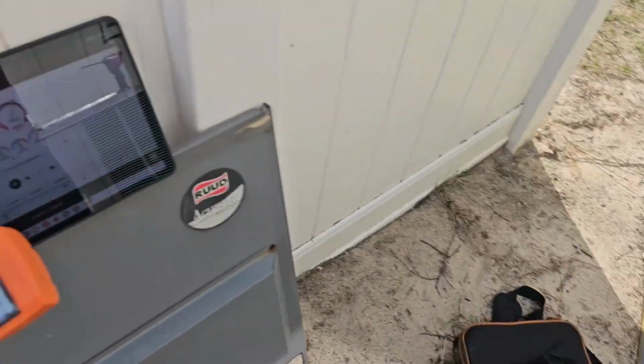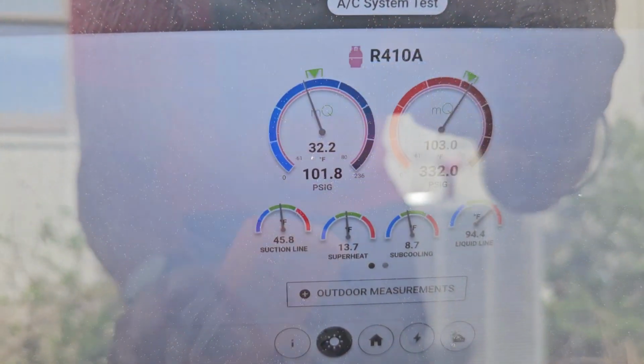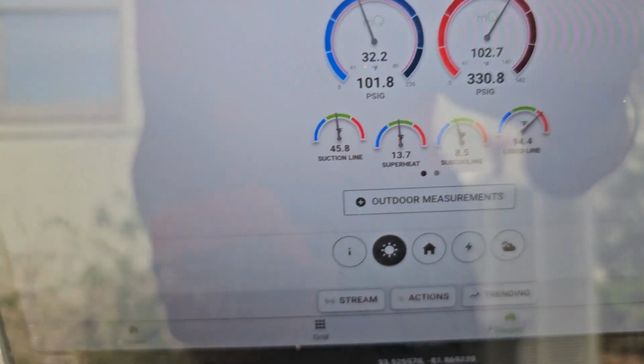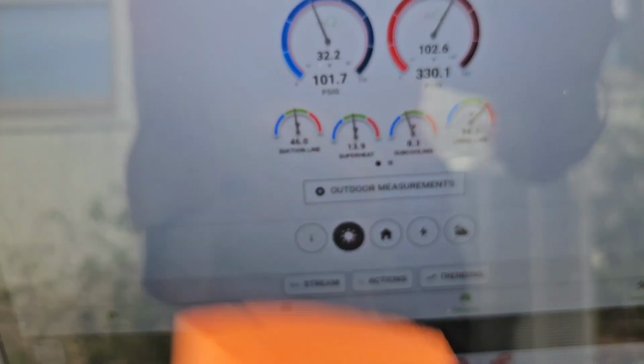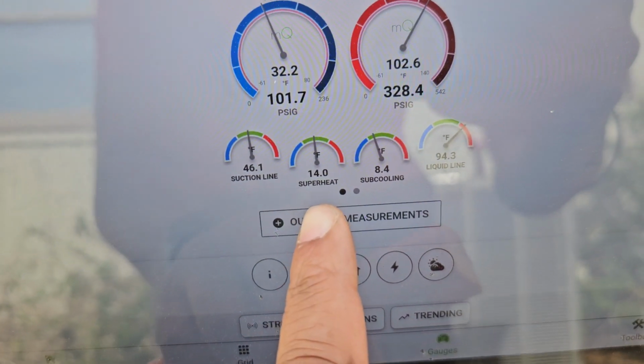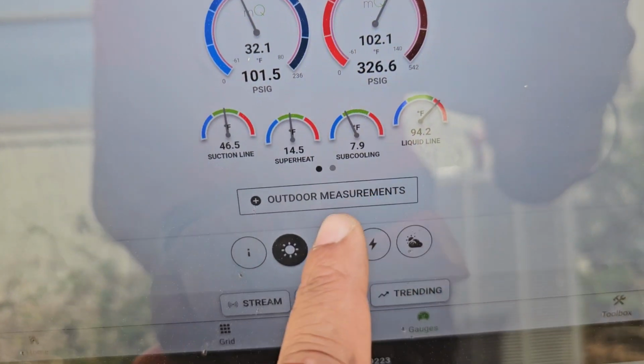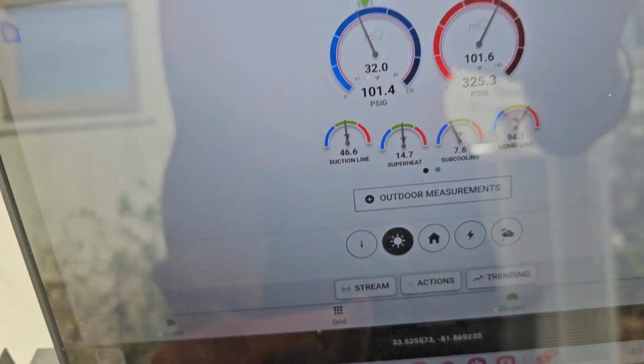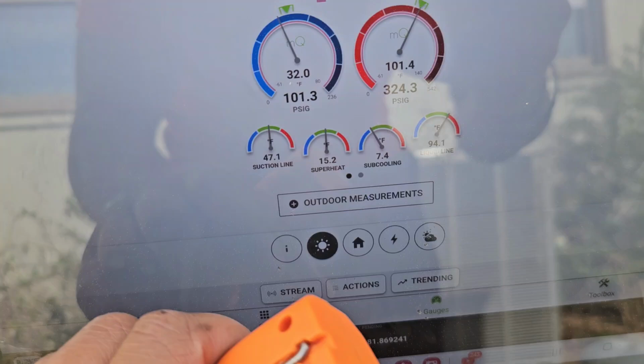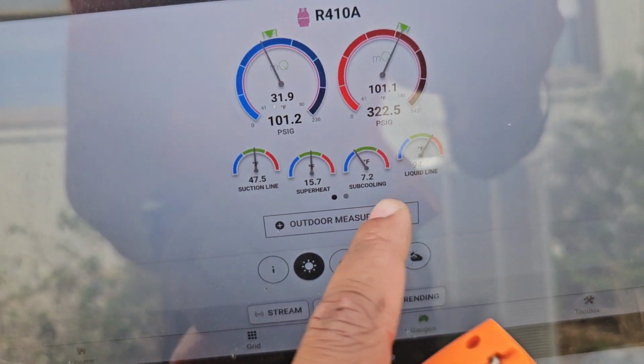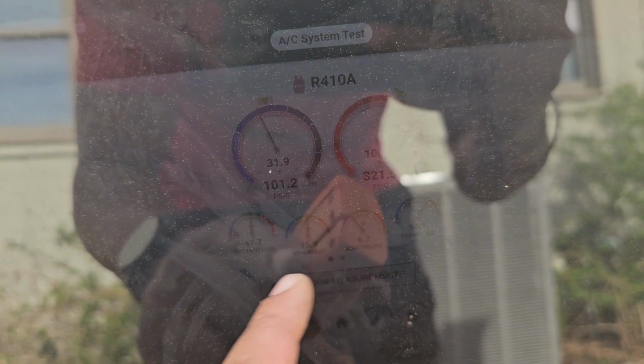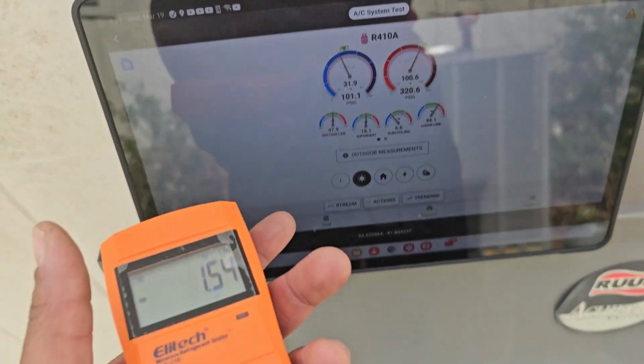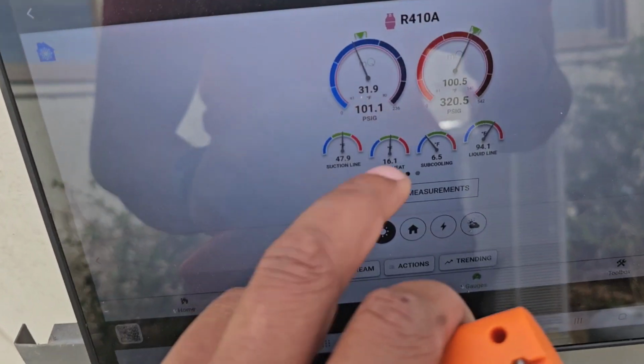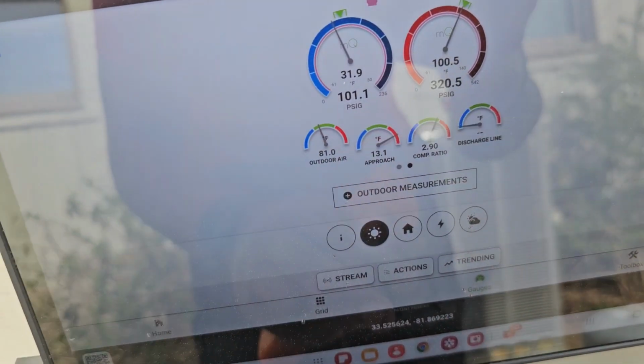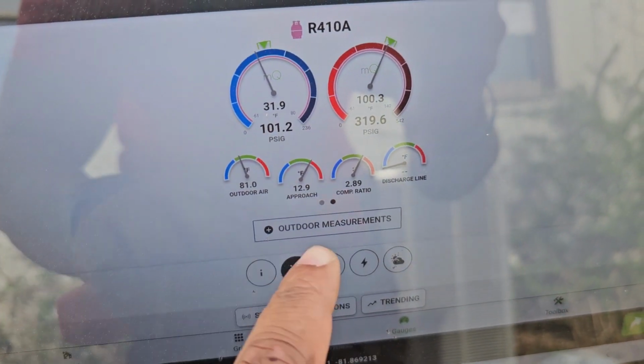Even though the homeowner came by literally at the end of the service call, this is what we're looking at now. After 1.5 pounds of R410A, we've got 14 degree superheat, and I got the subcooling up to 8, which I've always heard is fine, 8 to 12 for subcooling. We're in that green range, and I really don't want to overcharge this, even though if I did overcharge it, it's probably still fine because there is a leak. I did just talk to him about that, and he seems like he doesn't even want to dive into it like I thought.